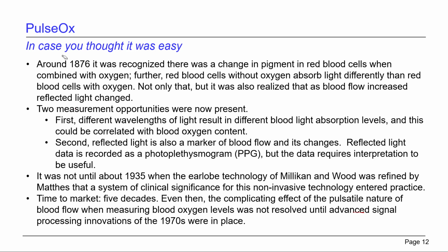The PowerPoint slides may make things look pretty easy, but the history can reveal a lot of insight as well. It really wasn't until 1876 that it was recognized it was a change in pigment in red blood cells when combined with oxygen, and furthermore, that the cells without oxygen absorb light differently than blood cells with oxygen. Okay? So on top of that, it was realized that as the blood flow increased, reflected light changed as well. So this created two measurement opportunities. First measurement opportunity was that different wavelengths of light actually have different absorption levels, and this could be correlated to blood oxygen content. Second was that the reflected light is also a marker of blood flow and its changes.